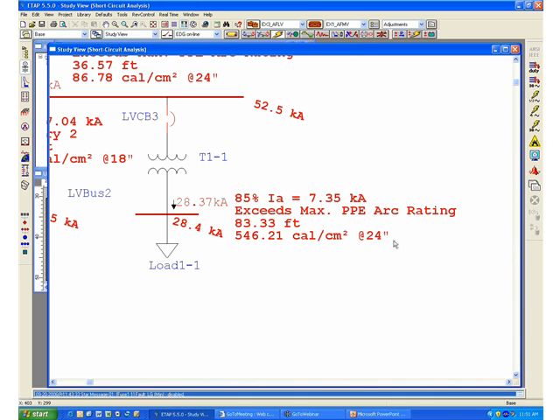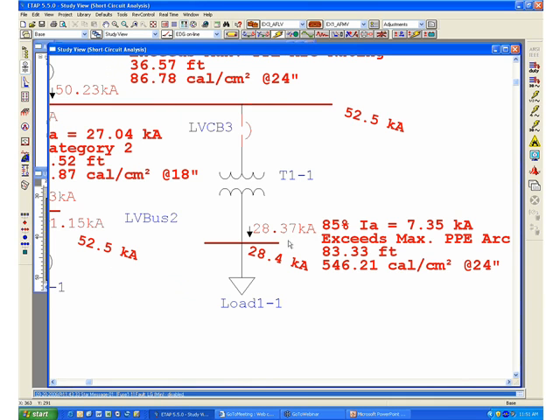For a fault on LV bus 2, the protective device that would trip the fault will be LVCB3.